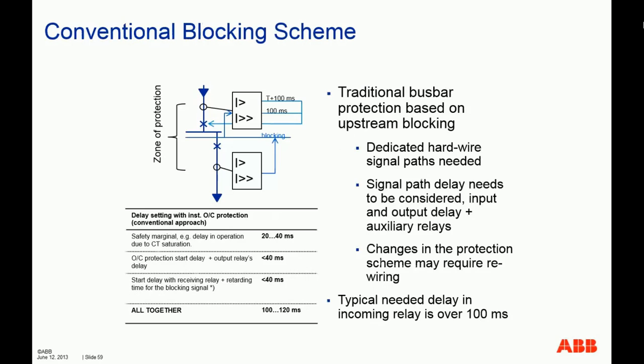So here's the scheme and also a tabulation of the time delay required. As you can see, this is traditional busbar protection based on upstream blocking. A dedicated hardwire signal path is needed from the output of the feeder back to the input of the main incomer, so signal path delay needs to be considered: input and output relay plus auxiliary relay. Changes in the protection scheme may require rewiring. So basically, you need to wire, but that's how it was done anyway before, with lots of wires between the relays. The estimated typical needed delay in the incoming relay is over 100 milliseconds.